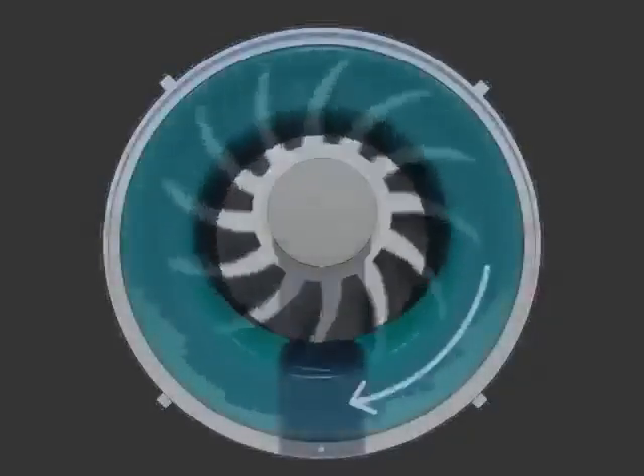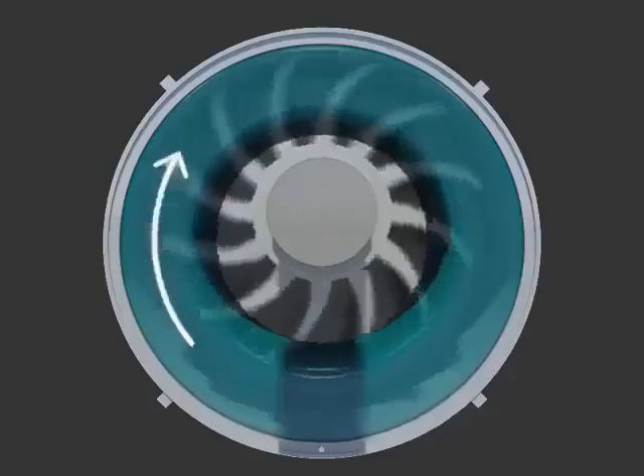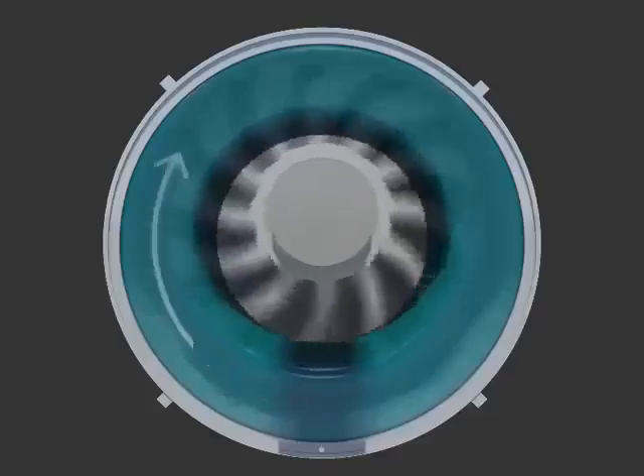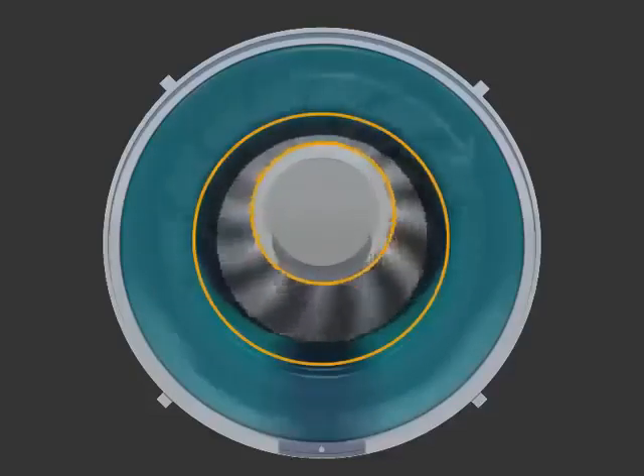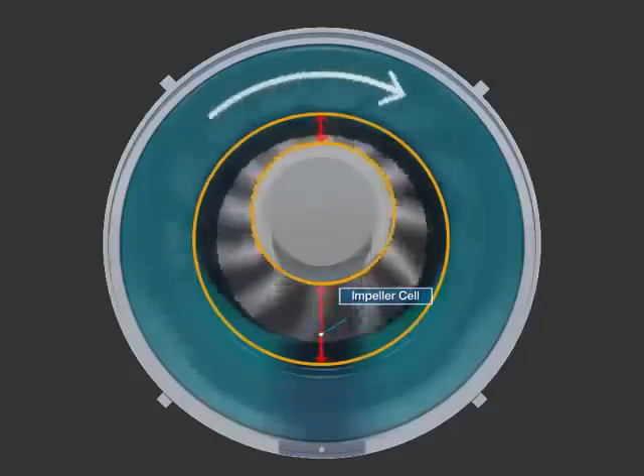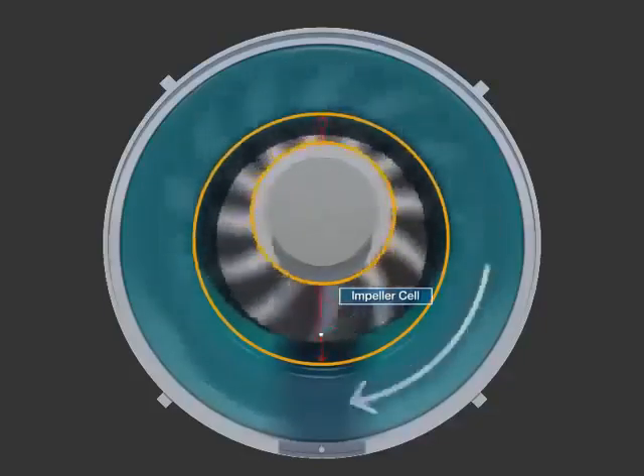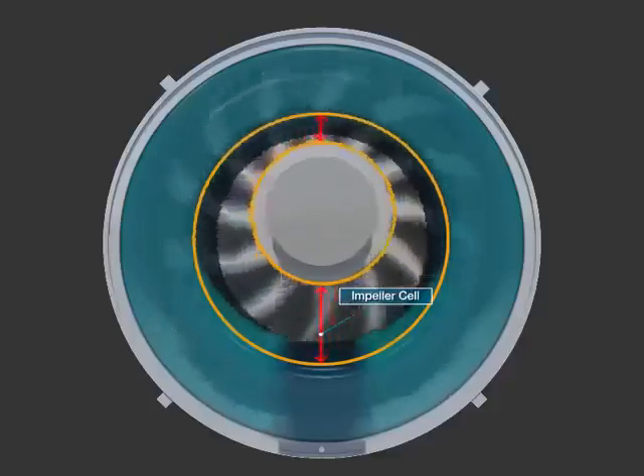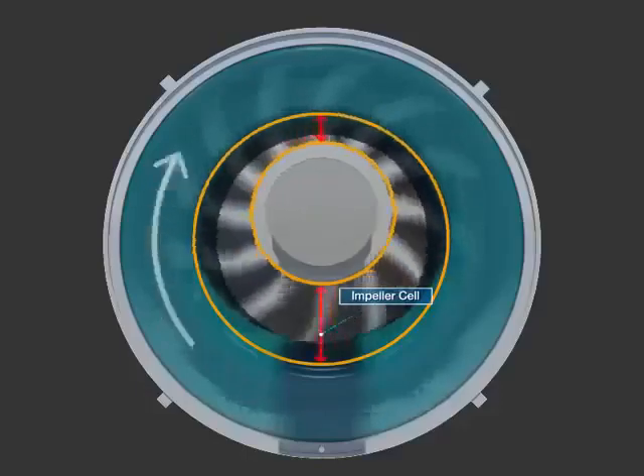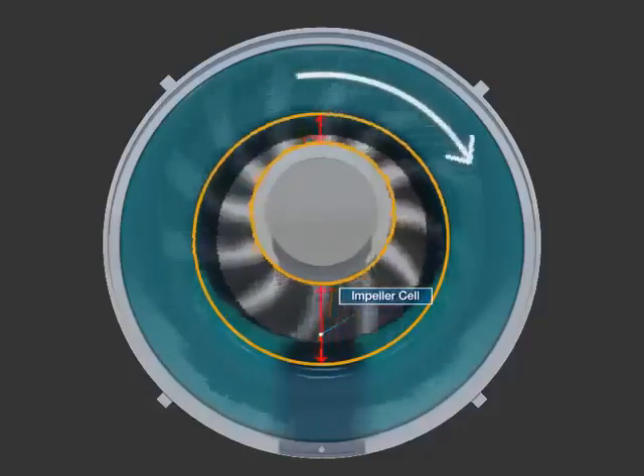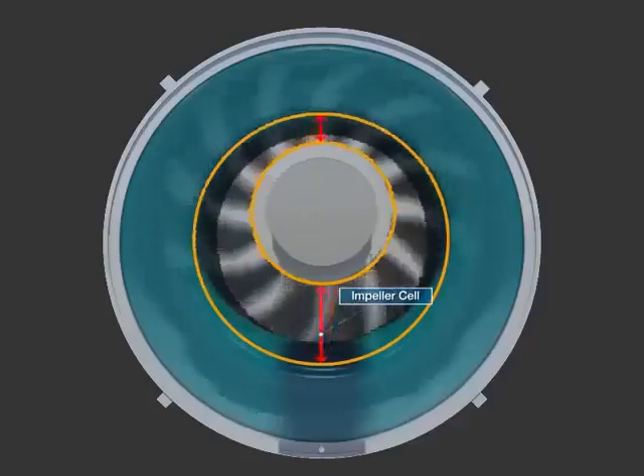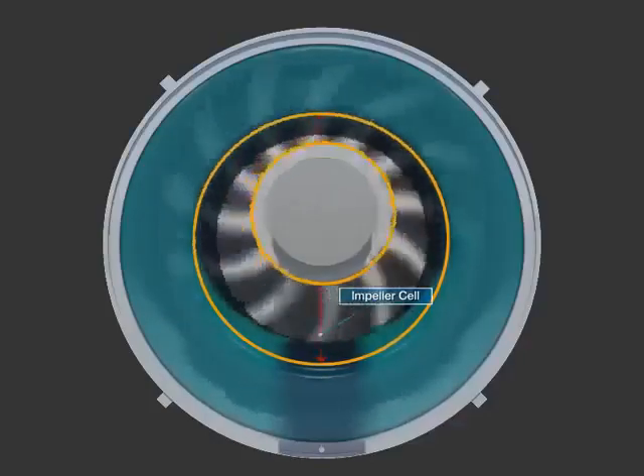The impeller spins at the speed of 495 rpm and the seal water becomes the form of a liquid ring because of the centrifugal force. The liquid ring, caused by the circulation of the impeller, creates a capacity differentiation between the impeller and the inner wall because the impeller is located at a biased position inside the casing.